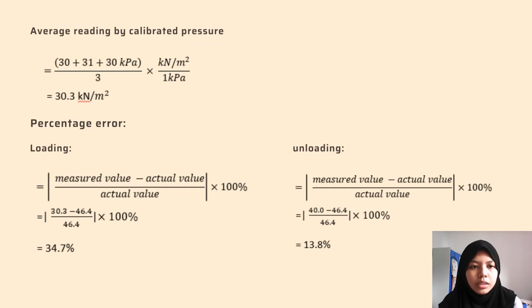And then we calculate the average reading by the calibrated pressure. We add all the pressures and divide by 3, and then we got 30.3 kilonewton per meter square. And then we are able to calculate the percentage error by using the values that we just calculated. So for the loading percentage error, we got 34.7%, while for the unloading, we got 13.8%.